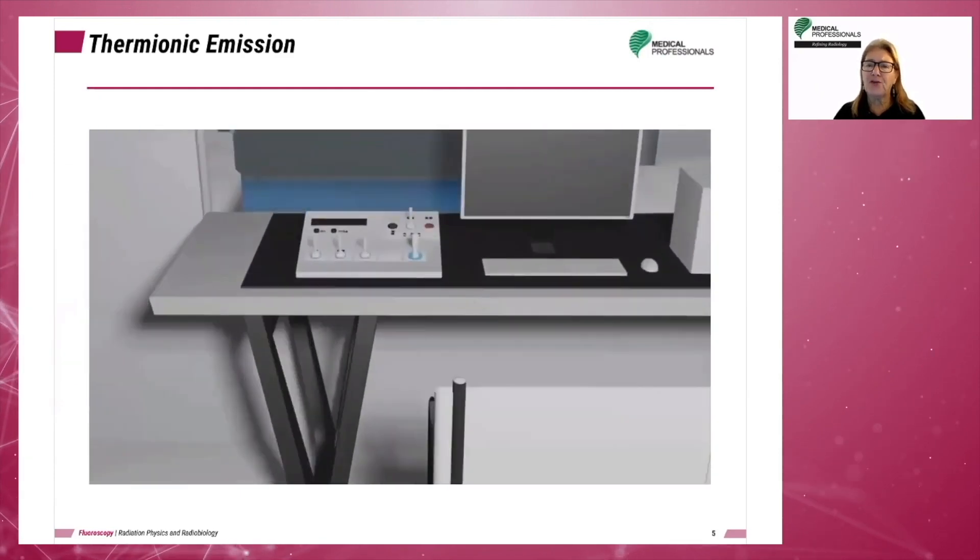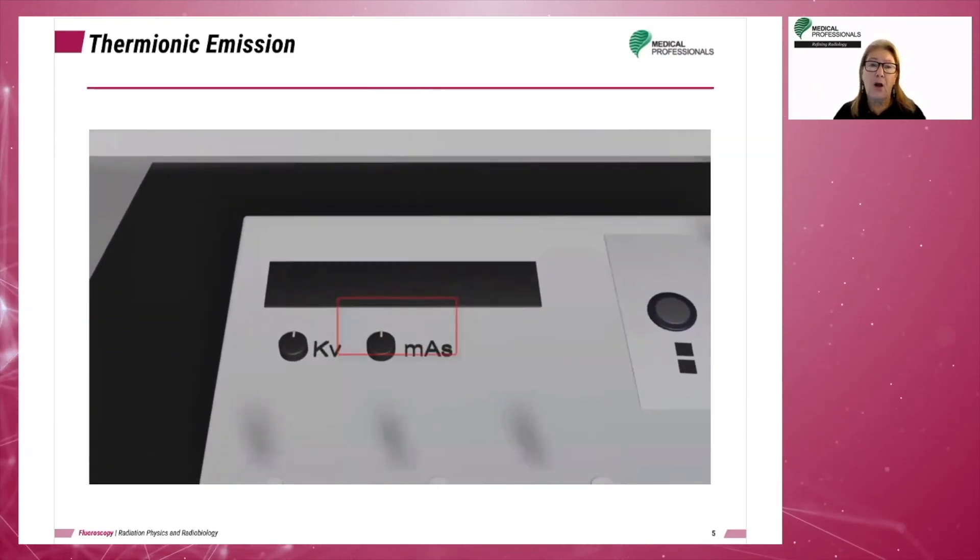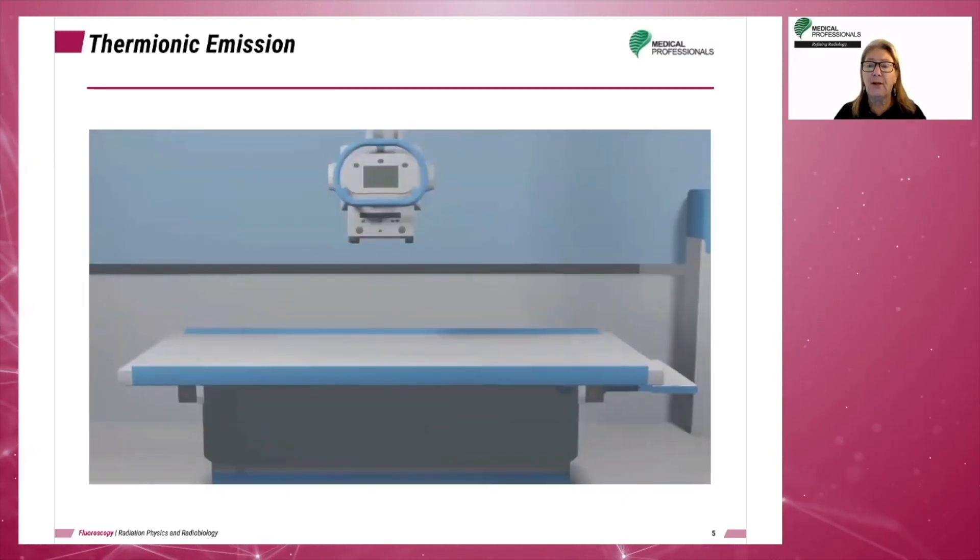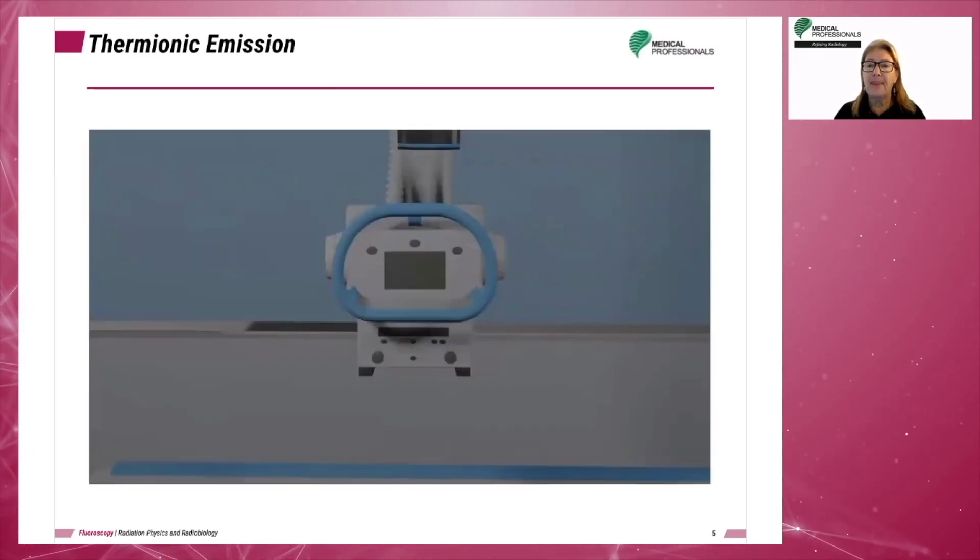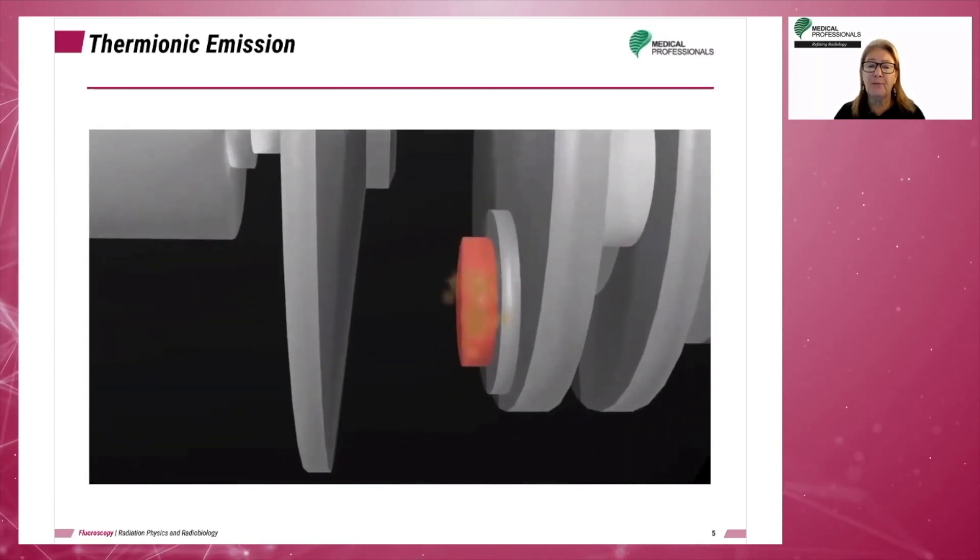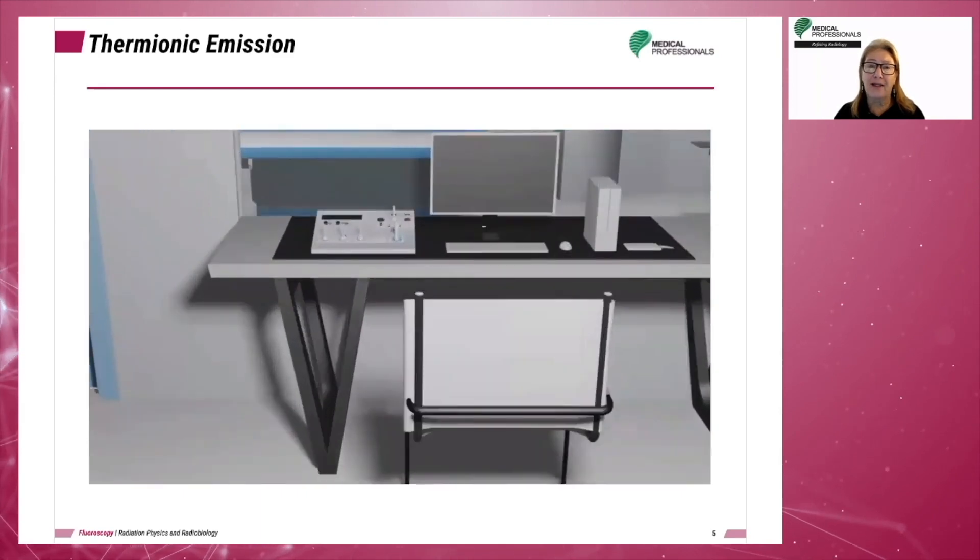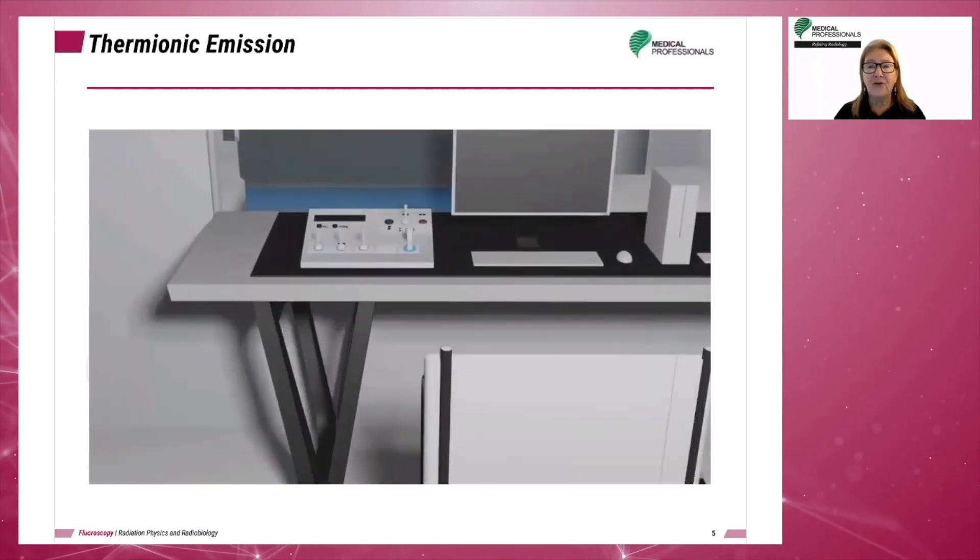When the rotor of an X-ray machine is activated, a small current causes electrons to boil off at the filament. The higher the mA, the more electrons will be present. This process is known as thermionic emission. The electrons float in a little cloud near the filament until voltage is applied to the tube.